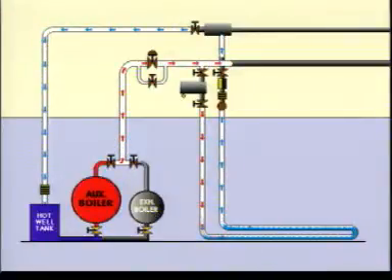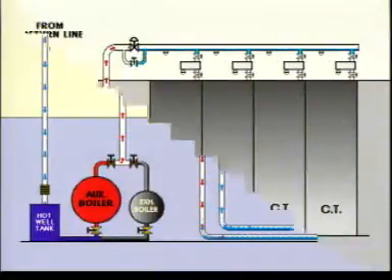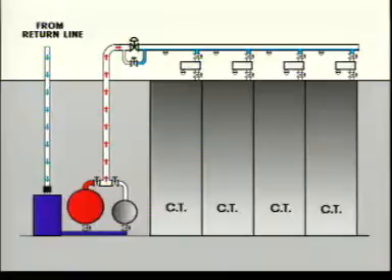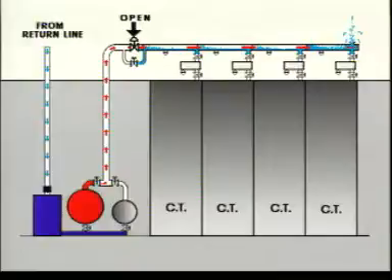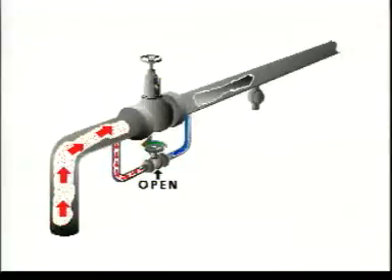It's important to take your time to warm the main steam line properly. If this long line is fed too much steam, it will cause strain. The main steam line may break, and you cannot heat the cargo until the line is repaired. So it's a good idea to first use the bypass valve when warming the main steam line.